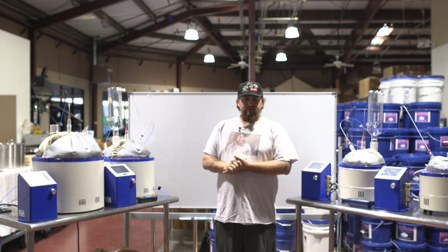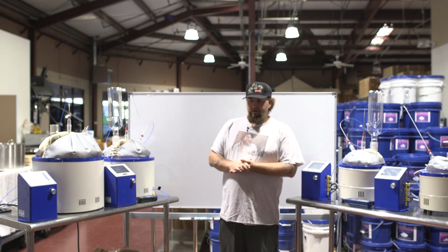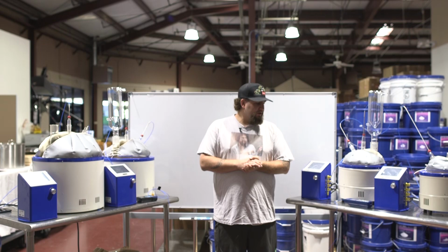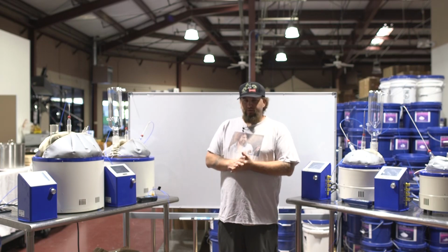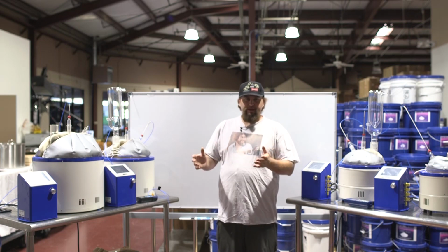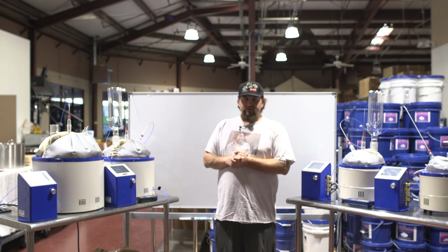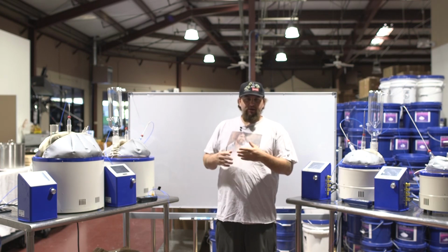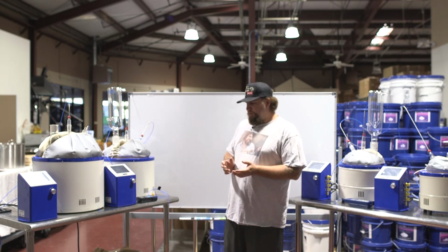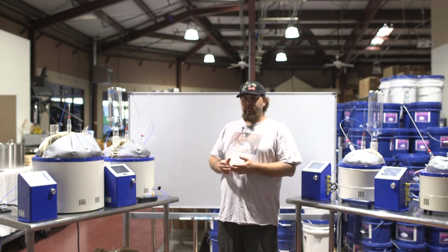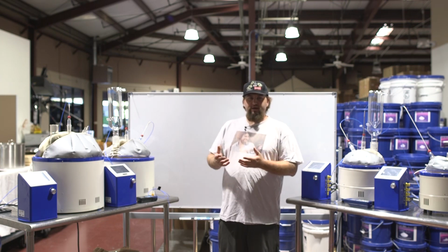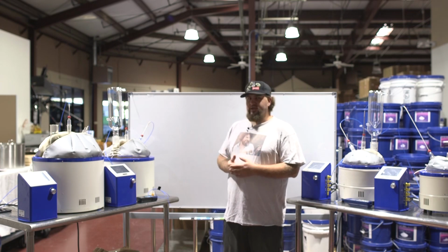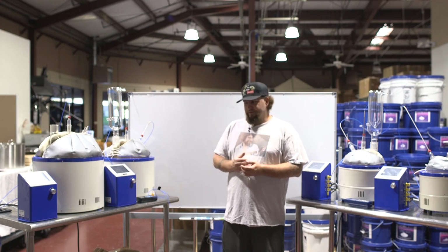So anytime someone brings us a product, we were able to go up against the standard, and we have every one of these units here standardized. So what's really important is that you can take a bunch of mantles from all different manufacturers and you actually put them side by side, and none of them are accurate. One of the ways that we are going to try to teach you guys how to calibrate something is by embedding the use of a traceable thermometer of such.